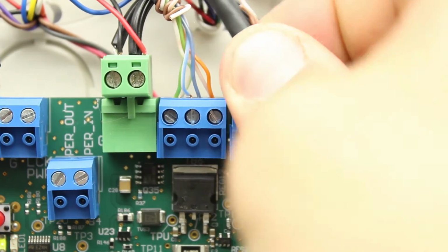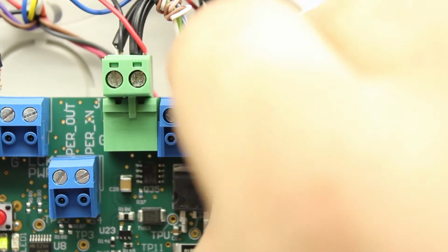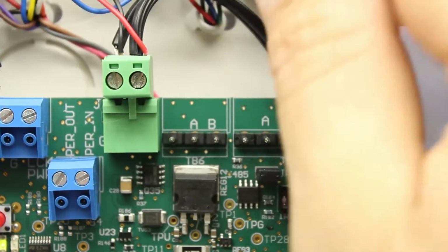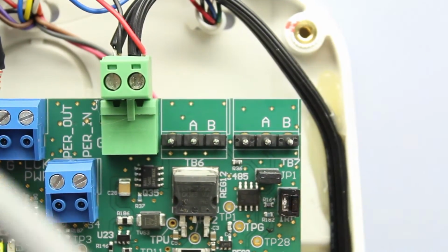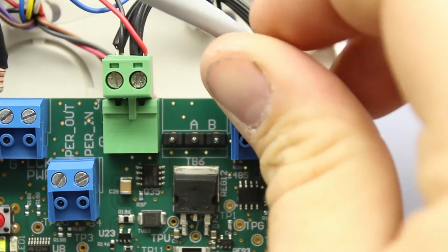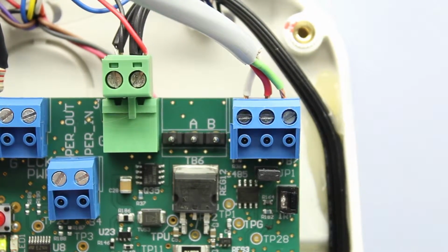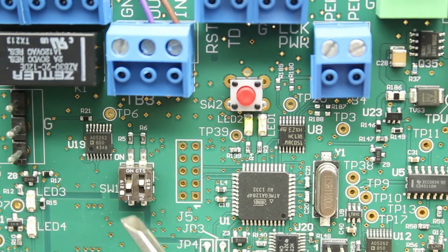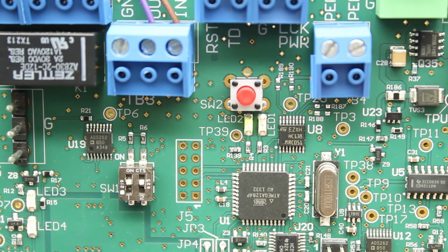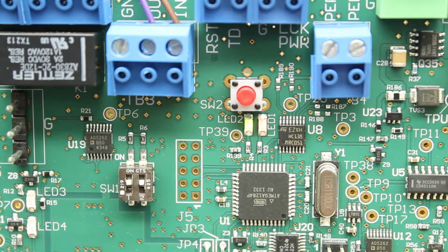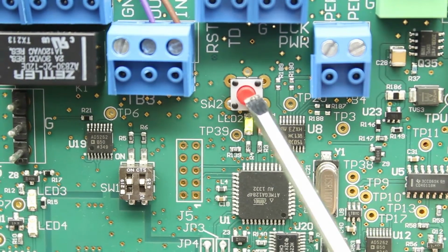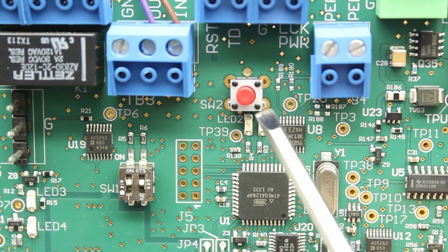Starting at the first door controller to be programmed, remove the Tek-CARE 700 network connections from TB6 and TB7. Connect the programming cable to either location. With the door controller powered on, set both switches on SW1 to the up position. This puts the door controller in programming mode. Cycle power to the unit by pressing the red reset switch.